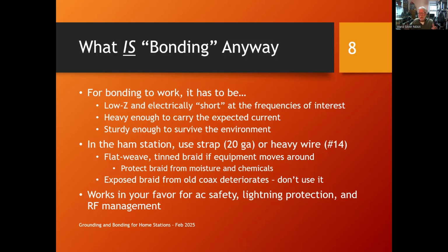So if you want to use that old piece of coax for something, just leave the braid in the coax, strip it at each end, waterproof it, put a terminal on it, and just use it as what I fondly call a BAW. That's a big ass wire. Okay, so you just have a nice big piece of wire that's as thick as a piece of coax with a terminal on each end. Works great, but don't strip the braid out and use it. Bonding, when you do it like this, and I haven't talked about any special conductors or anything like that that's really expensive, works in your favor for all three of those sets of requirements: AC safety, lightning protection, and RF management.